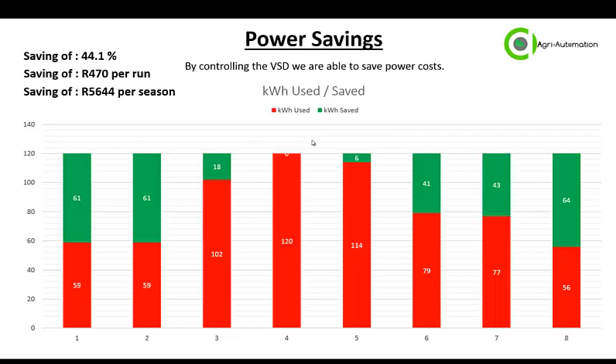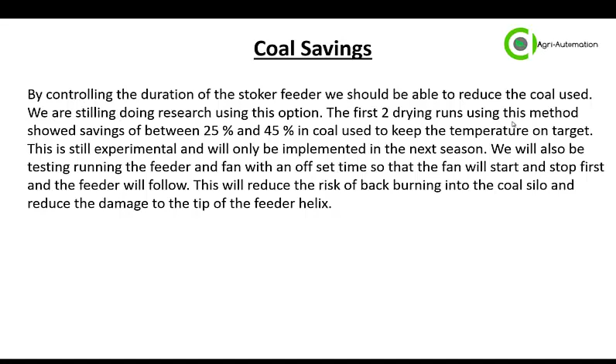We're controlling the duration of the stoker feeder by pulsing it on and off during a burn. This new season that's coming up, we'll test this a lot more, but initial tests show that we can save between 25 and 45% in coal usage. We're also going to offset the feeder with a fan, so that the fan will start blowing first for about 15 seconds, then the feeder will kick in 15 seconds later, pulse on and off, and then once on temperature the fan will switch off, but the feeder will still turn, pushing coal into the fire. This will help to reduce back burning into the coal silo and to reduce damage to the tip of the feeder helix.